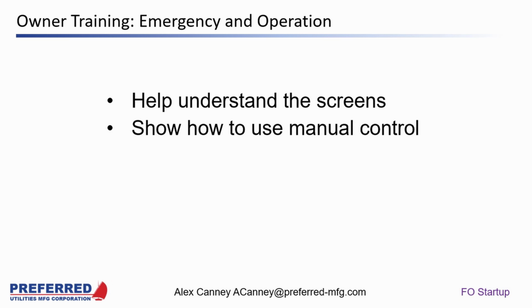But that being said, especially if we have a multi-day tank system, it's very important, if we're running this in manual, what are some of the considerations that we want to have? Let's say the PLC or the controller's down, and we've now made the decision to turn pump 1 on in hand or on manual. What do we need to make sure of at that point? Well, it depends on if it's a single day tank or a multiple day tank. If it's multiple, then 99% of the time there's going to be a control manifold to each one of the day tanks. With the PLC being down, that means there's no power to the solenoid valves that are keeping that closed. So you're hoping that the system was designed with a bypass line on it.